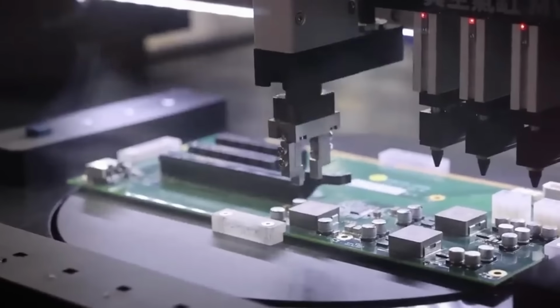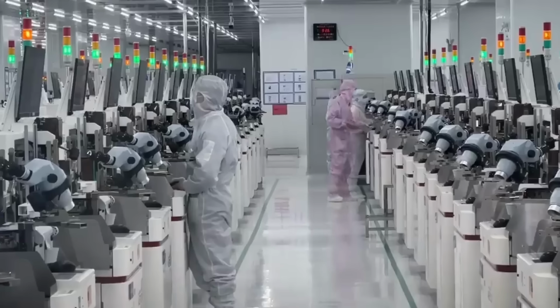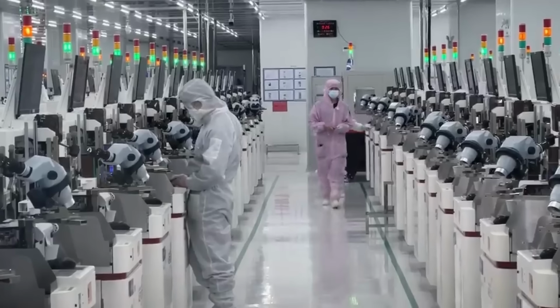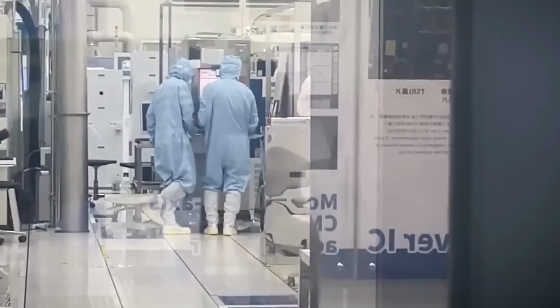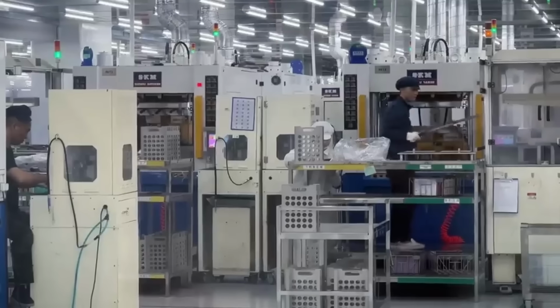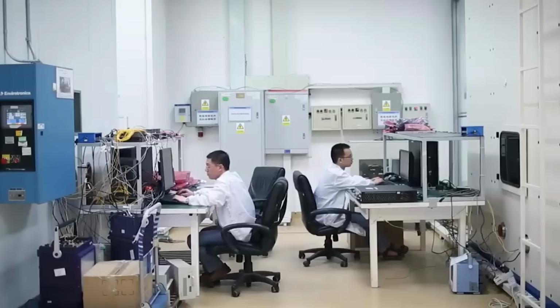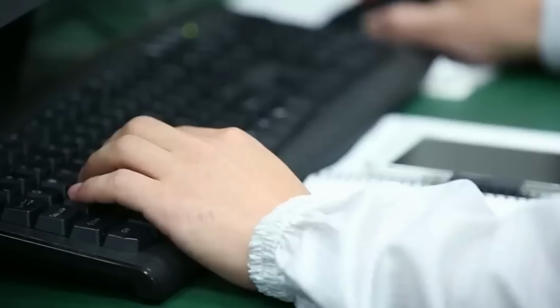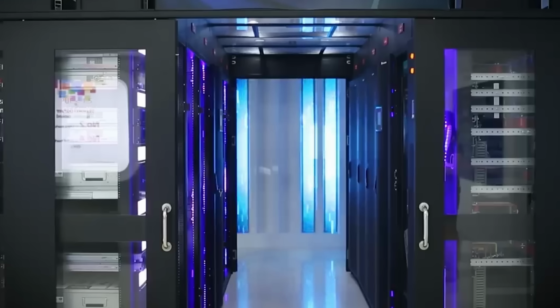Each GPU generates heat like a small space heater running at full blast. Multiply that by 1 million, and you've got a thermal nightmare that would turn a conventional facility into a giant oven within minutes. Traditional air cooling? Completely useless at this scale. Even the most advanced air systems couldn't touch the heat output these processors generate under full load.